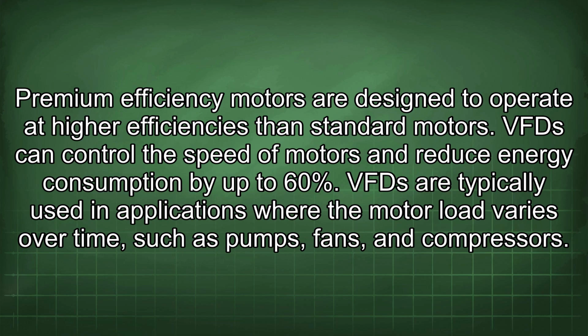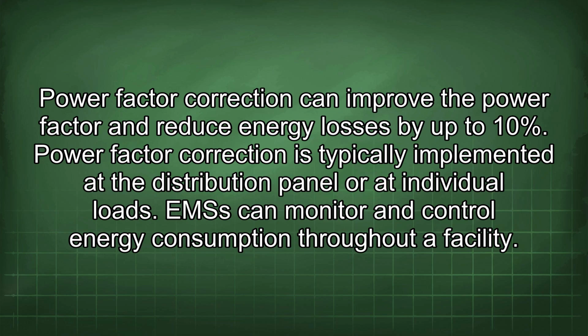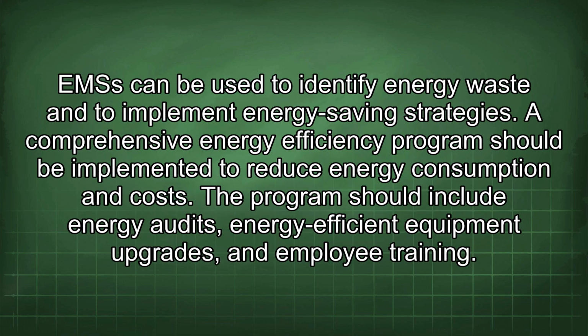VFDs can control the speed of motors and reduce energy consumption by up to 60%. VFDs are typically used in applications where the motor load varies over time, such as pumps, fans, and compressors. Power factor correction can improve the power factor and reduce energy losses by up to 10%. Power factor correction is typically implemented at the distribution panel or at individual loads. EMS can monitor and control energy consumption throughout a facility. EMS can be used to identify energy waste and to implement energy-saving strategies.